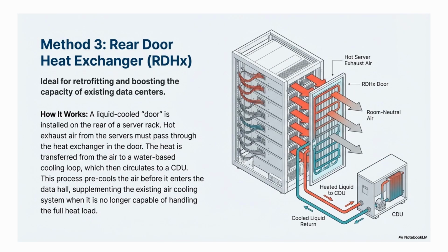But what about all the data centers that are already built and can't just do a total refit? Right. They still need to boost their cooling. That brings us to our third solution, the rear door heat exchanger, RDHX. The RDHX is the pragmatic choice. It's the immediate, effective retrofit solution for an existing air-cooled data center.